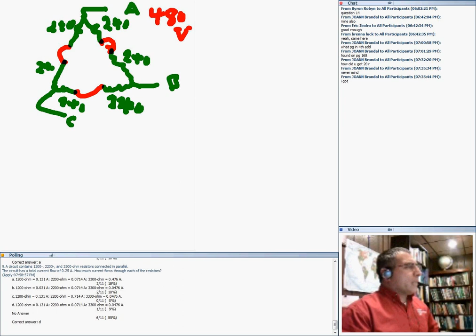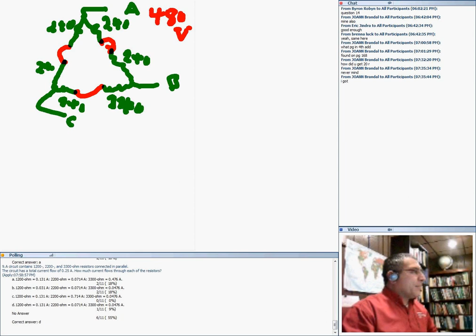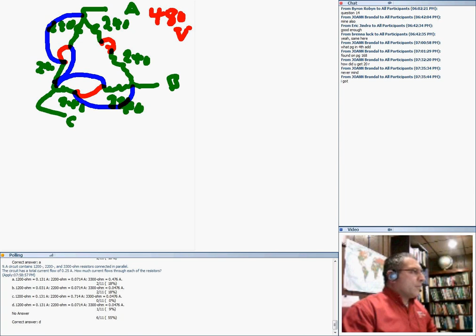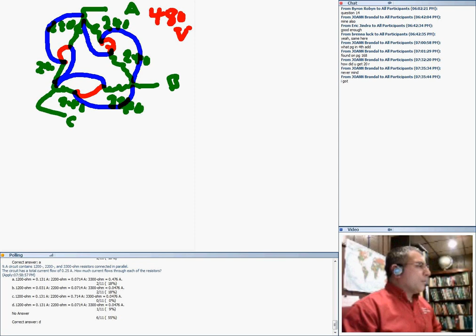Now if I run the same motor and go to a building where the only system available is 240 3-phase, you can still connect them, but this needs some explanation. When you connect these - it might get messy here - I bring this coil to this end, and this coil to this end. These 2 coils are now in parallel. The same thing: take this coil to this end, and this coil to this end - just examine the hookup. If I do it this way, these 2 coils right here are actually in parallel.